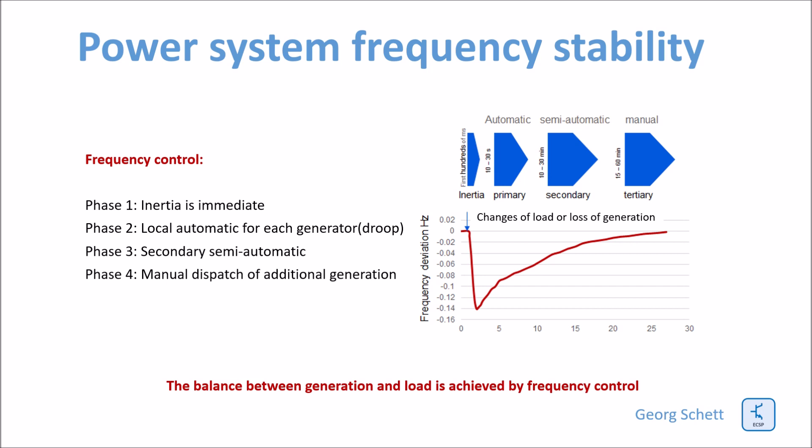The frequency control is performed as follows. After a change of the load or a loss of generation, there are three consecutive phases. The first phase, phase one, is immediate. And in this phase, the demand is met by using the stored energy in the rotating mass of the generation involved.